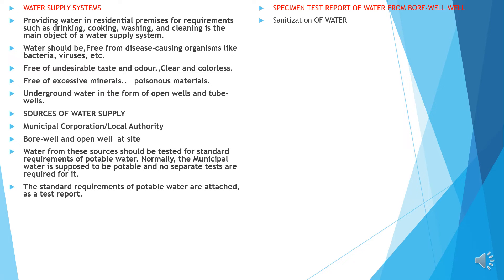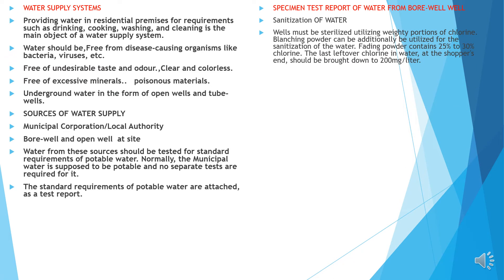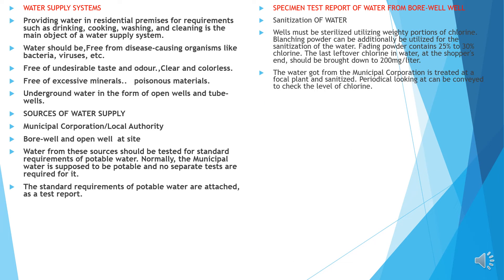Sanitation of the water: wells must be sterilized using heavy doses of chlorine. Bleaching powder can additionally be utilized for sanitation of the water. Bleaching powder contains 25–30% of chlorine. The residual chlorine in water at the consumer end should be brought down to 0.2 mg per litre. The water from the municipal corporation is treated at a local plant and sanitized. Periodic checking can be carried out to check the level of chlorine.